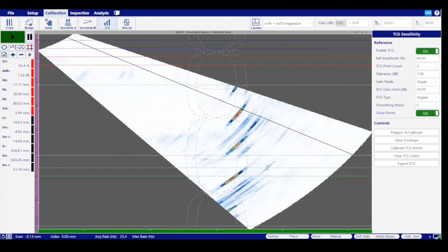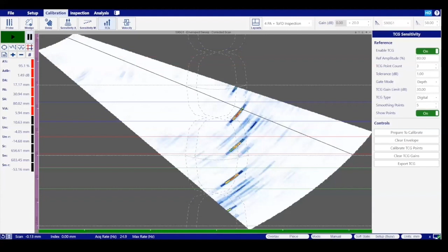So these 3 gates can be used to simultaneously capture the indications coming from 3 of our reflectors. We simply put our gates on the 3 reflectors which we have chosen, set our gate to cover the entire range, and we can start capturing our envelope. Okay. Clear the envelope, and as we move, as you can see here, all the gates are capturing simultaneously, and you can also see the corresponding envelope on the right.